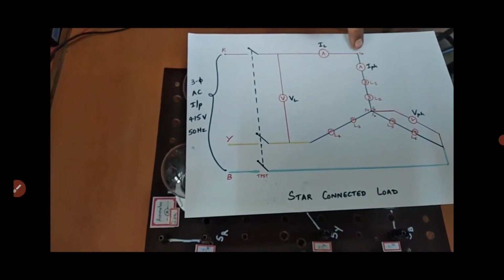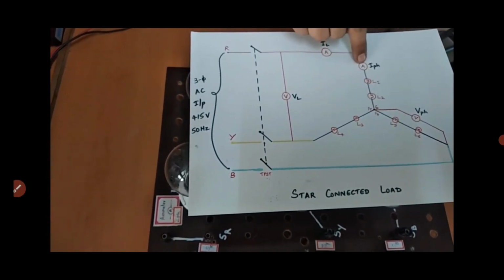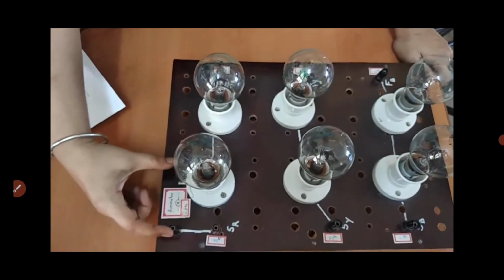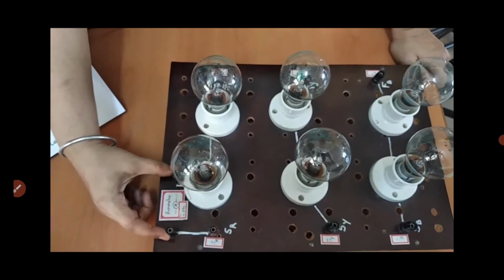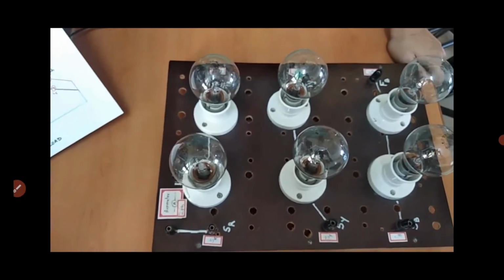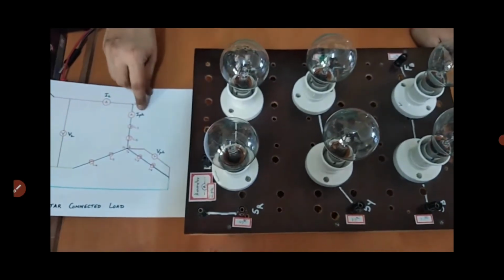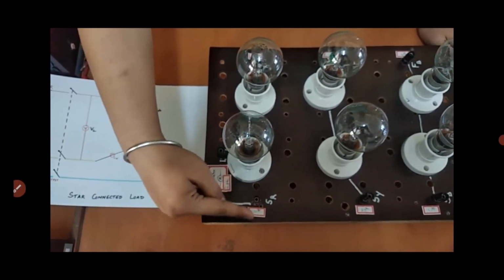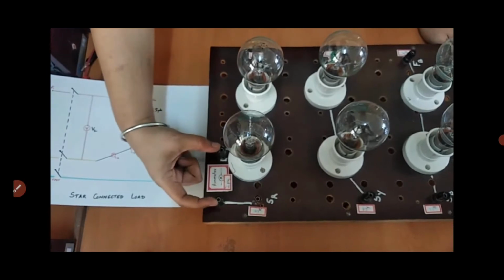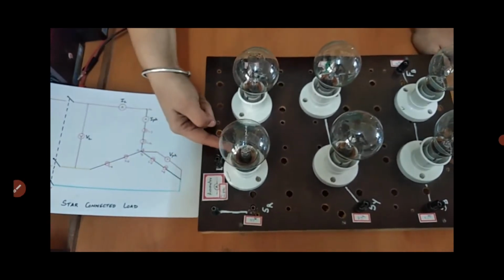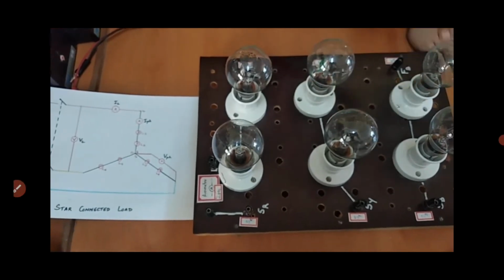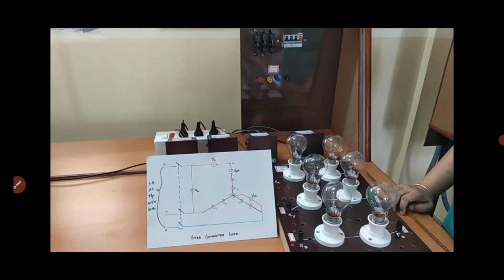So we know after SR we have an ammeter. Here we also have the provision for ammeter connection. So SR, ammeter L1 and L2. SR one terminal will be connected here. This is the ammeter L1, L2 and finish. Then connect the circuit as per the circuit diagram.